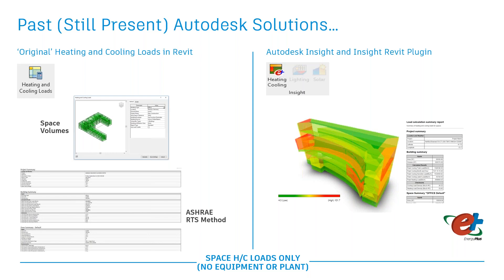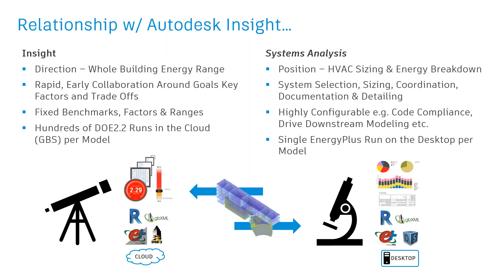People might be interested in the relationship between this new feature and Insight. Insight is our early-stage energy analysis tool that provides overall direction and whole building energy range — rapid early collaboration around key goals. It uses DOE-2 and runs in the cloud, running a few hundred simulations per model. Whereas systems analysis runs a single EnergyPlus run on the desktop but is much more detailed. Insight is like a telescope — it provides direction. Systems analysis provides position: very high precision and control over virtually every input.